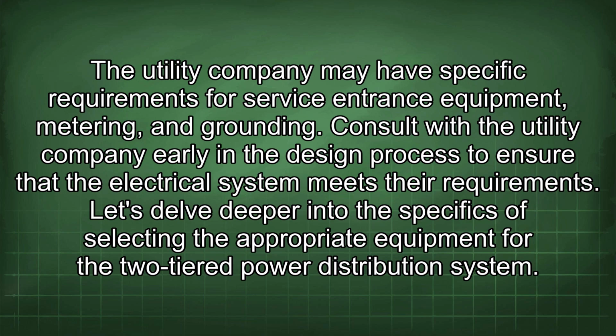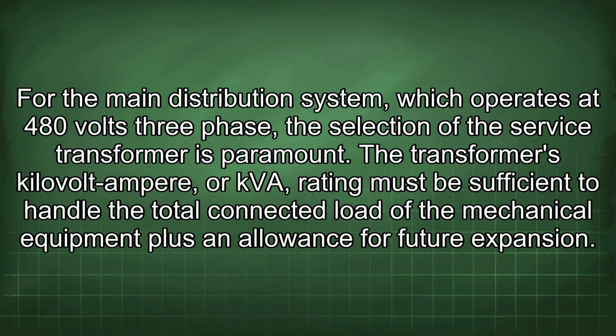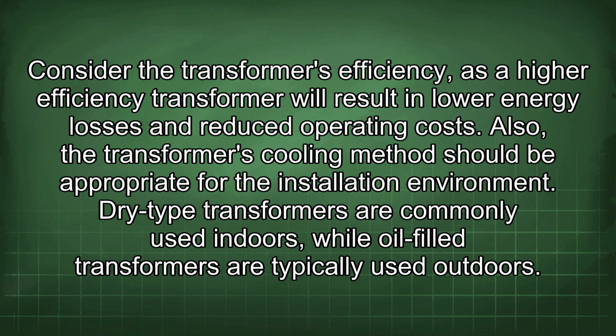Let's delve deeper into the specifics of selecting the appropriate equipment for the two-tiered power distribution system. For the main distribution system, which operates at 480 volts three-phase, the selection of the service transformer is paramount. The transformer's kilovolt-ampere, or kVA, rating must be sufficient to handle the total connected load of the mechanical equipment plus an allowance for future expansion. Consider the transformer's efficiency, as a higher efficiency transformer will result in lower energy losses and reduced operating costs. Also, the transformer's cooling method should be appropriate for the installation environment.